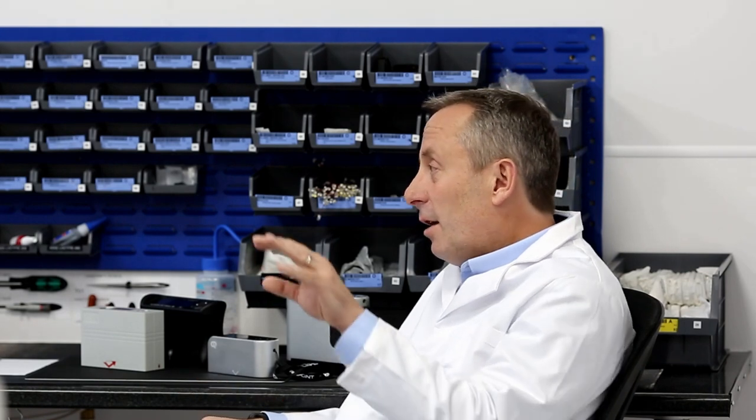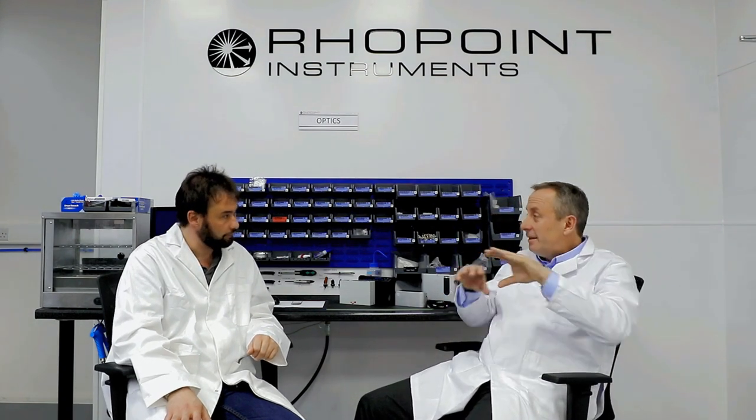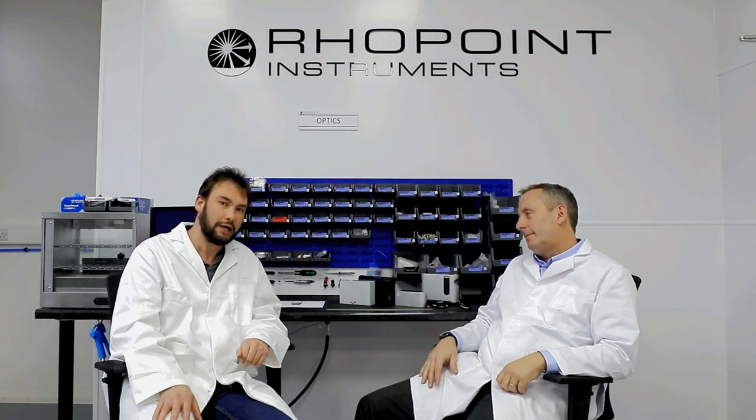So by the sounds of it, the tech is really in the sensor and the interpretation of the data coming out of the sensor, rather than the actual LED light, which is fairly generic. Yeah, we have to filter it. Again, in the standards you have to have a certain colour of light coming out of the LED, so we have to change the colour of the light to match the standard. That's in Kelvin, I guess, a K rating on the light? It's actually, there's a committee called the CIE which determines light. It's the spectral response, so how much green and red and blue is in the light source, and it's CIE C in the gloss meters. Gotcha. So essentially we're getting an idea of how gloss is measured, what gloss is.